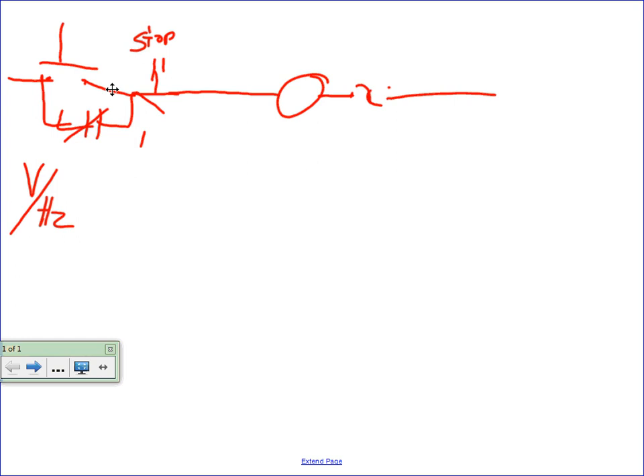But what we're doing is, you've got this AC coming into the drive. I'm not going to try and draw it, but we've got a rectifier system, a DC rectifier, full bridge. So it basically converts the AC to a DC voltage. And in the output, we have six IGBTs that convert it back into three-phase AC. Well, actually, we are pumping DC voltage to an AC motor and thinking it's getting AC, and that's what pulse width modulation means. We actually vary the width of the pulse.